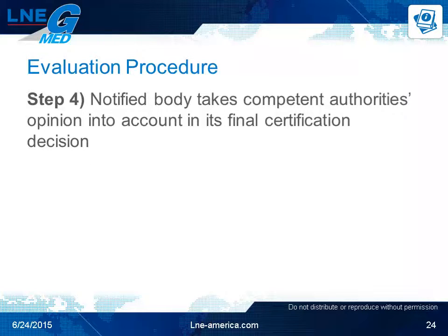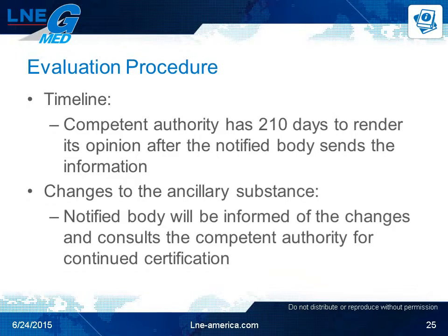The fourth step, notified body takes a competent authority opinion into account in its final certification decision. As many of you are concerned about the competent authority's evaluation timeline, upon receipt of the full file, the ANSM proceeds to an evaluation of the file eligibility within 15 days.